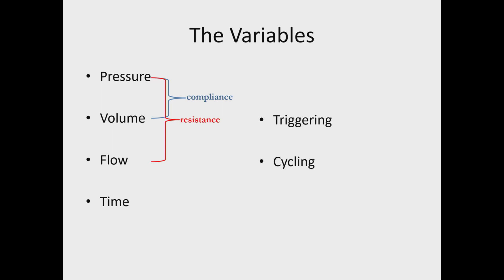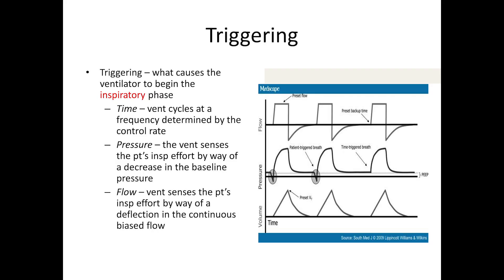We also have some control over triggering and cycling. Triggering is what really begins the inspiratory cycle — it's what tells the mechanical ventilator that it's time to begin the inspiratory phase of respiration.